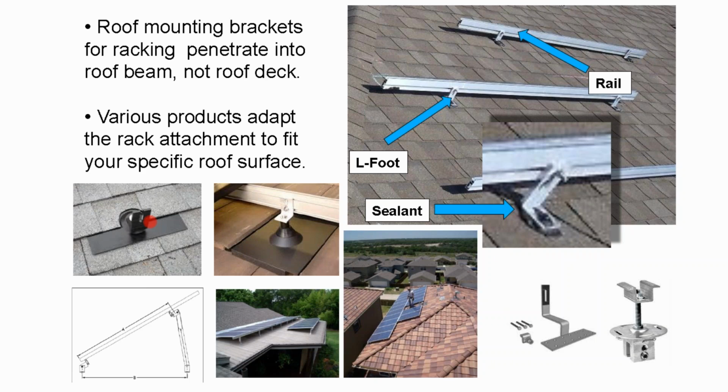The most important thing when you're putting a solar array on a shingle rooftop is to respect the fact that every step you take on that roof is getting grit off of the shingles. So the least amount of time you spend on the rooftop, the better, which means you want to prepare as much as you can on the ground before getting up on the roof. But for tile roofs, there's a tile replacement. There are kick-up legs you can get. The Spanish tile roof hooks, like this, that kind of snake out and through the Spanish tile are largely being replaced now with full tile replacement.